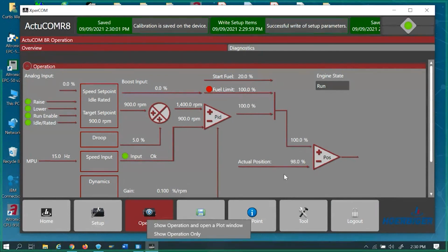I've had some calls from some guys that had this set at like 80-something before, and they said, well, I can't run my engine fast enough. I said, well, either you got to give it more fuel or you got to give it more actuator, one or the other. So right now I'm at 1400 and I'm only at 900. My governor's all the way open. So quickly I'm just going to bring my RPM up.